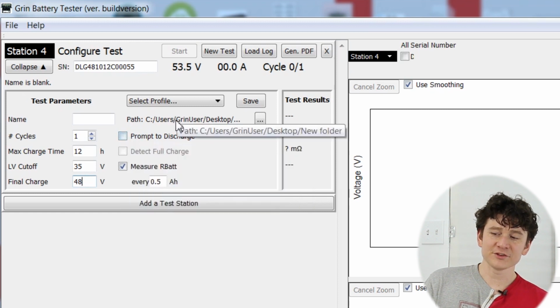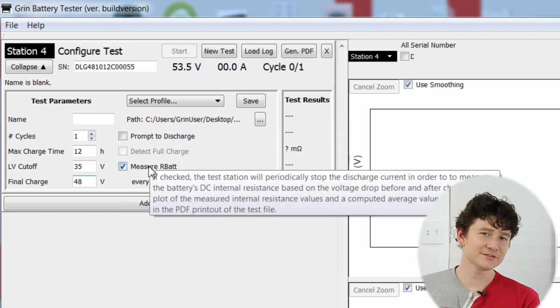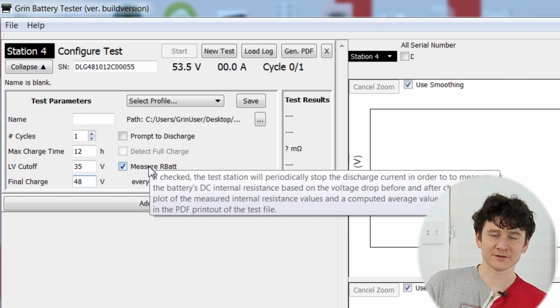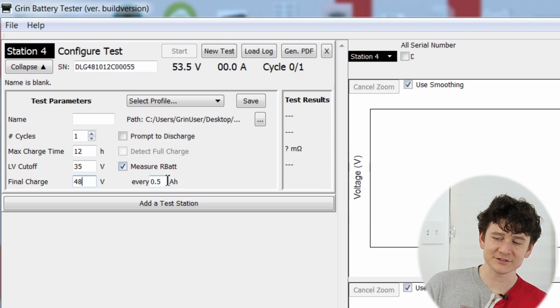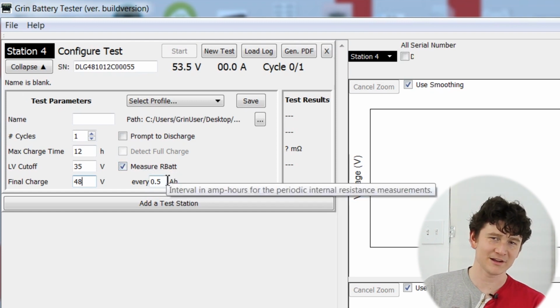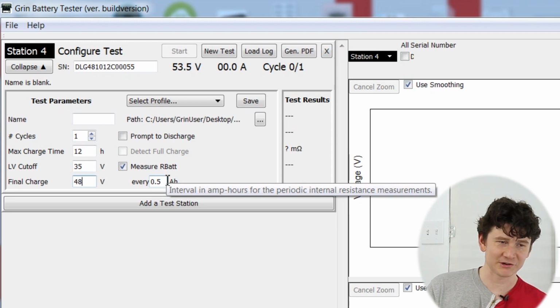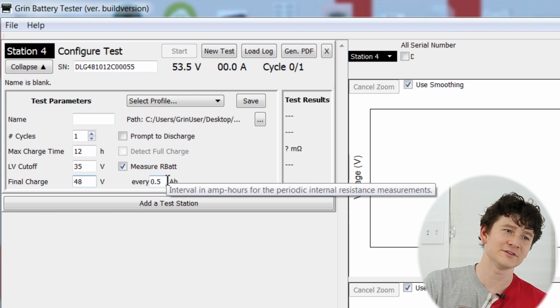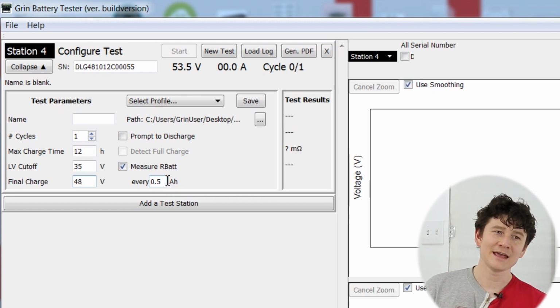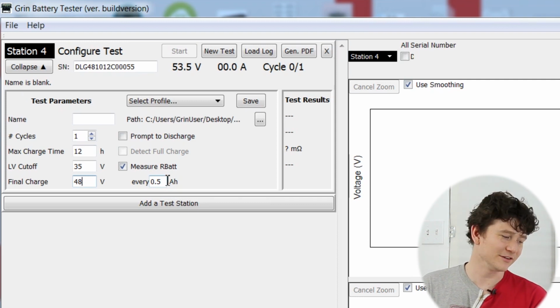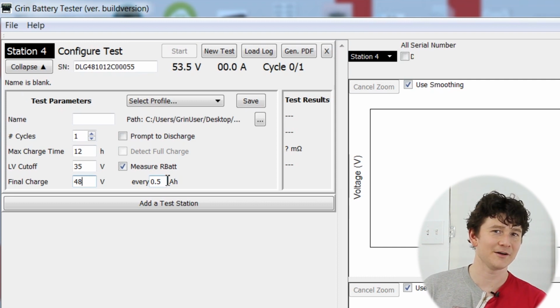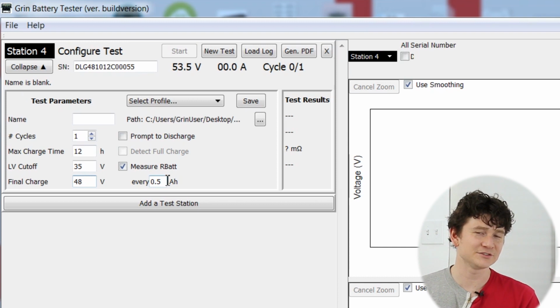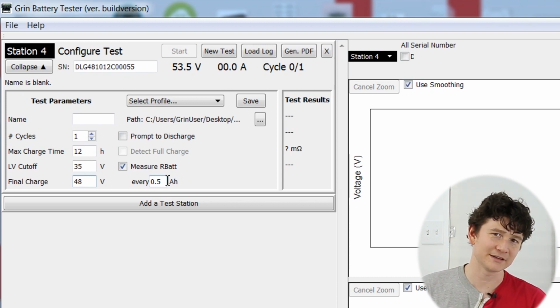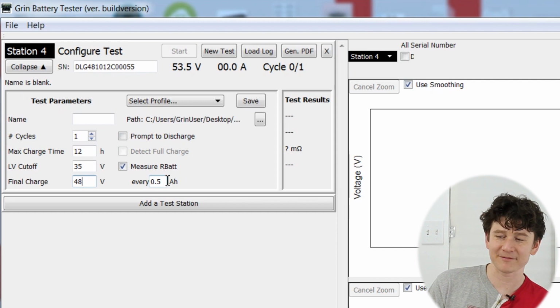The fields on the right are more advanced. This one, Measure RBatt, is a new feature in our 2020 Grinspector software suite, allowing the station to assess the internal resistance of the battery periodically during discharge. It does this by pausing the discharge current briefly and seeing how much the voltage rebounds, then drops again when discharge resumes. By looking at that voltage change relative to the known current change, it can estimate the internal resistance of the cells, a very useful data point for assessing battery health. With older batteries, capacity might decrease only a little, but you often see a noticeable increase in internal resistance, giving a better assessment of where the battery is in its lifespan.